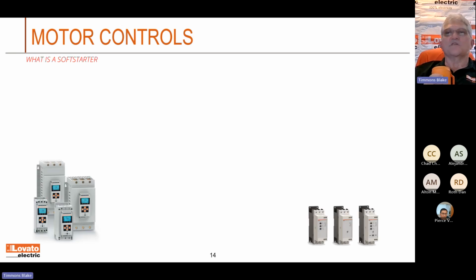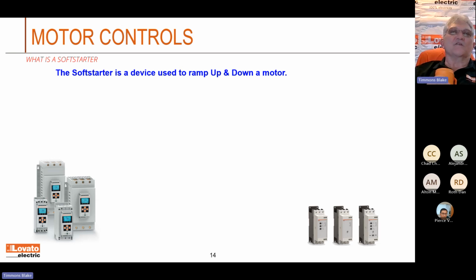Okay, now we go into a soft starter. What is a soft starter? I get a lot of people trying to buy soft starters and VFDs and not really sure which way to use it. But basically, a soft starter is a device used to just ramp up and ramp down a motor. All you're trying to do is cushion the mechanical load on it and kind of shave off that peak demand when you get a big surge. You're trying to shave that off a little bit.